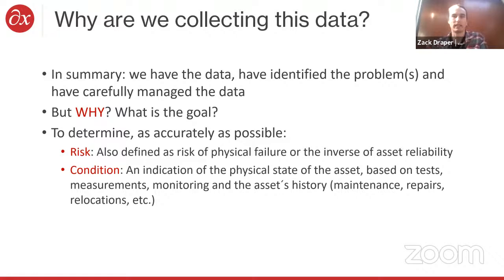The reality is that condition-based maintenance - only a small subset of testing is actually based on condition. If you're doing electrical testing, power factor testing, that's the condition of the transformer, but it's very expensive to do and requires de-energizing a transformer. So we want to eventually determine the condition of the transformer, but what we're often left with is using statistics to determine the risk involved in operating it.